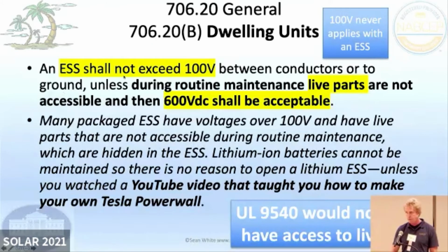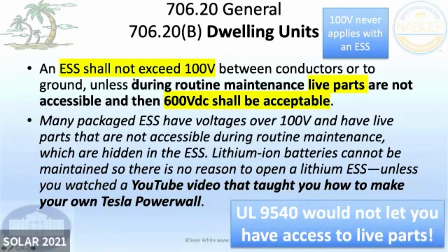This is another thing about the NEC that's just confusing. It says an energy storage system shall not exceed 100 volts. This is also for a dwelling, and it usually just means a 1 and 2 family dwelling. And then it says, but if you don't do maintenance on live parts, you can go up to 600 volts. You look at a lot of these energy storage systems, and it's just like, what comes out of it?